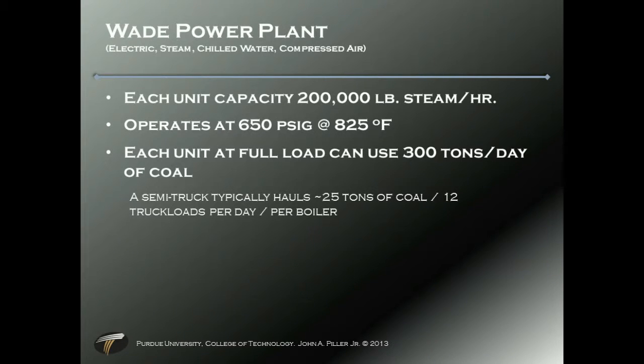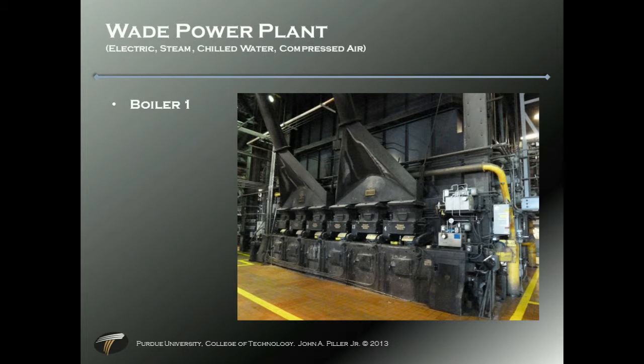Boiler number 2, a spreader stoker coal unit, enters the boiler via mechanical belts, and it's slung into the firebox also. So what do we mean by that? There are fingers in every other position along a belt that are throwing coal into the air. It actually ignites in the air and burns mostly before it hits the ground. By the time the coal hits the very bottom of the firebox, it's already ash at that point.